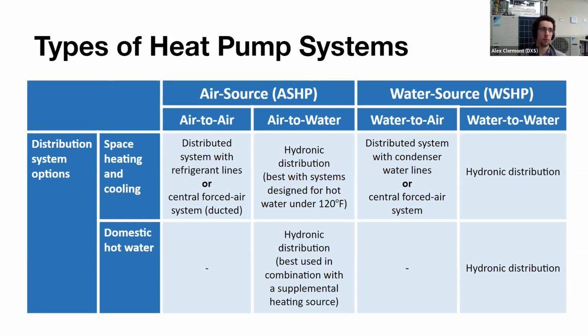So in an air source heat pump, if you just hear the term air source heat pump, that's usually referred to as an air-to-air machine, where an outdoor machine is extracting and rejecting heat to the outside air and then delivers heating and cooling to the space with refrigerant lines tied to a ductless or ducted central unit. Now, this can also be air to water, and we're going to talk about air to water heat pump chillers in a little bit, where the outdoor unit rejects and absorbs heat from the outside air, but delivers heating or cooling to the space using water. These types of systems could also help with domestic hot water as well.